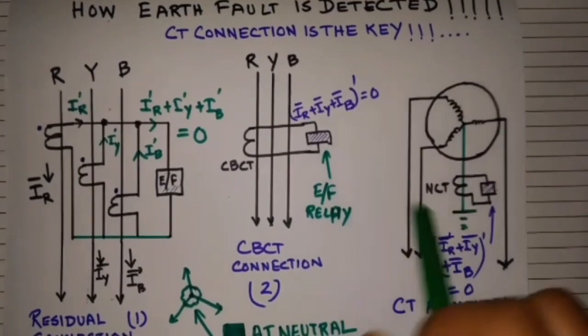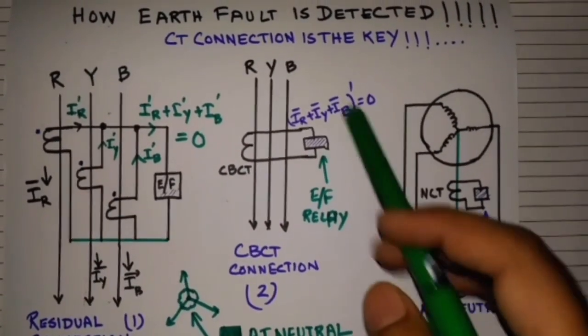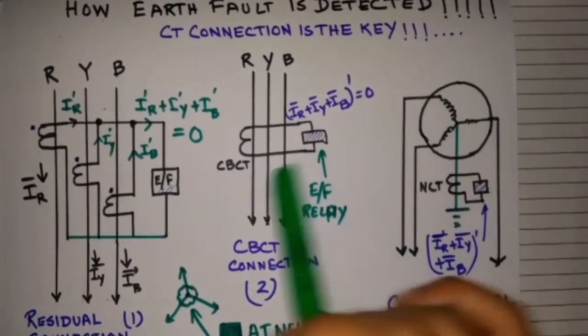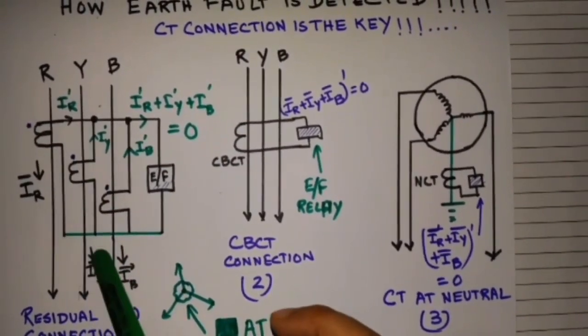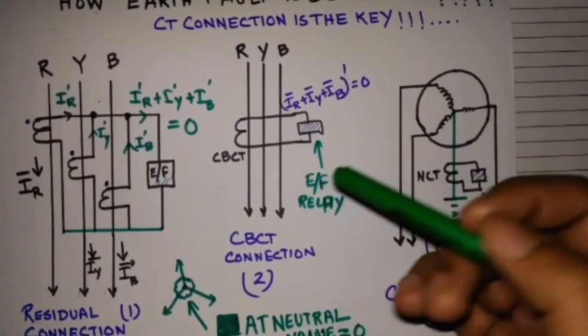So these three are the basic principle, basic CT connection, by which the earth fault is detected. The earth fault relay has no such special element. It only detects the earth fault due to their CT connection. The CT connection is such that it can only be energized during an earth fault. For any other type of fault, it will not energize.